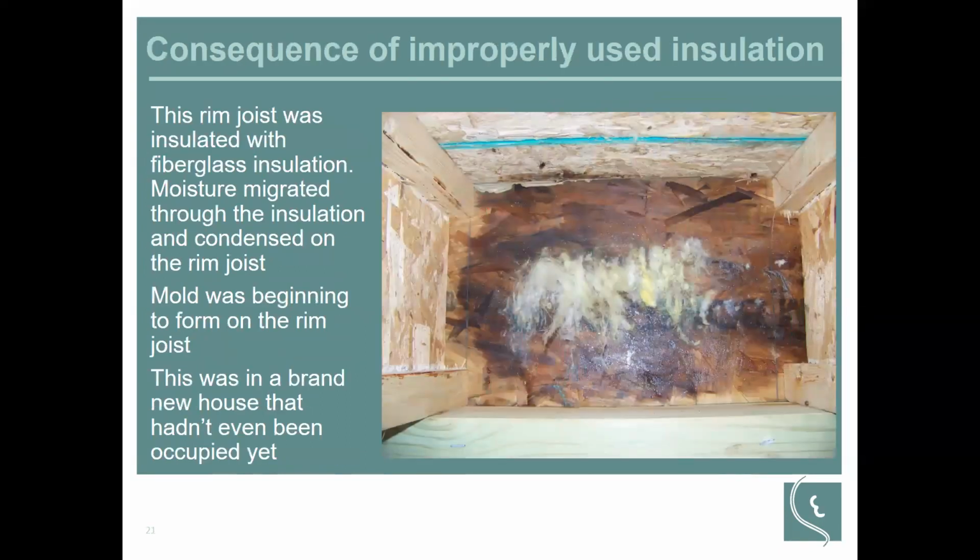I mentioned fiberglass insulation isn't very good at stopping air. Well, air also carries moisture with it. This was in a brand new home that hadn't even been occupied yet. I was down in the crawl space with the site superintendent, and I asked him if I could pull a piece of insulation out between the joists there. He said, sure, go ahead. I pulled it out, and lo and behold, I knew what I was going to find: all kinds of moisture condensing on that rim joist.